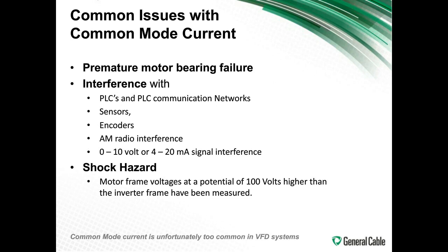What we see, the common issues, and you can see this, is with the motor bearings. If you see premature motor bearing failure, it's very likely that that's from the cable not being adequate for your system and the common mode current issues with that. You can see interference from PLCs, PLC communication networks, sensors, encoders, AM radio interference, all sorts of possibilities. You also see shock hazards because there are voltage potentials created along the inverter frame and motor frame that are really high, sometimes close to 100 volts higher.